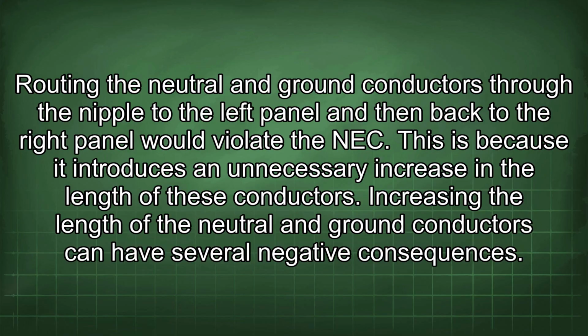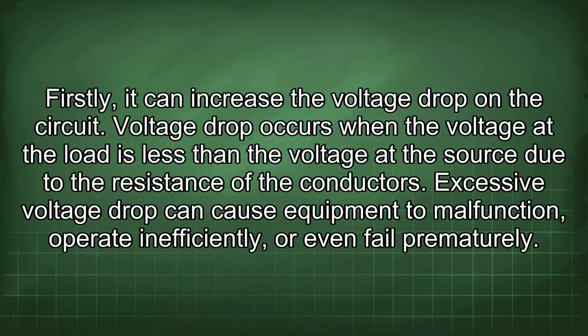Increasing the length of the neutral and ground conductors can have several negative consequences. Firstly, it can increase the voltage drop on the circuit. Voltage drop occurs when the voltage at the load is less than the voltage at the source due to the resistance of the conductors. Excessive voltage drop can cause equipment to malfunction, operate inefficiently, or even fail prematurely.